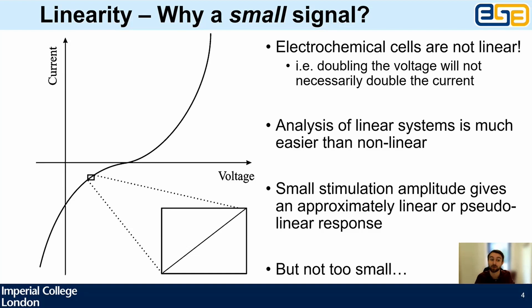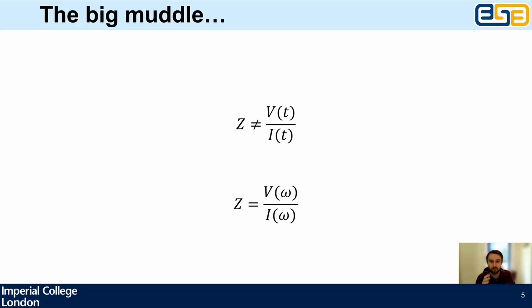Don't make the signal too big or it'll be non-linear, but don't make it too small or you'll have a signal-to-noise problem. That's why you pay good money for high-quality impedance equipment — it can generate small signals and measure them accurately across a wide range. The key insight is that impedance is not the ratio of voltage and current in time — it's voltage and current in frequency.